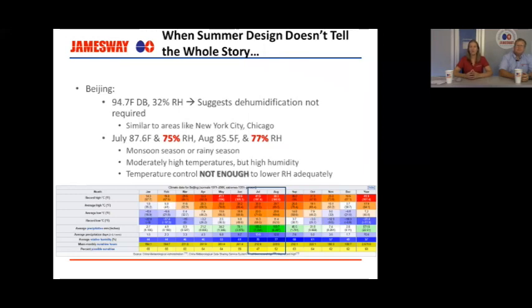The other problem is summer design doesn't tell us the whole story. So we're going to use Beijing as an example here. Beijing has a 94.7 degree Fahrenheit summer design temperature, 32% relative humidity. That tells me they don't need dehumidification. That's similar weather to areas like New York City, Chicago, Toronto. You maybe have a few weeks in the summer where it gets pretty humid, but as a whole, on their hottest days, it wouldn't be humid enough to require dehumidification.